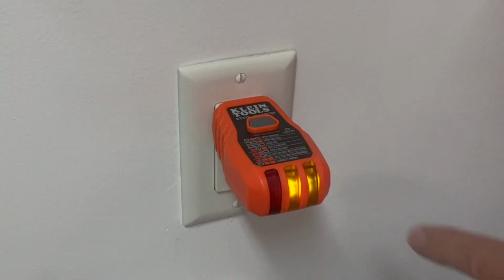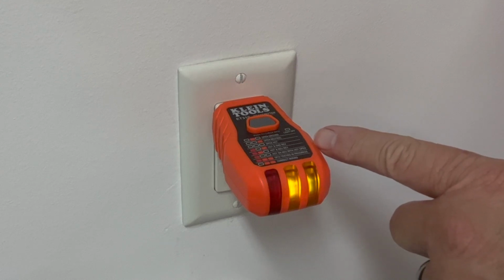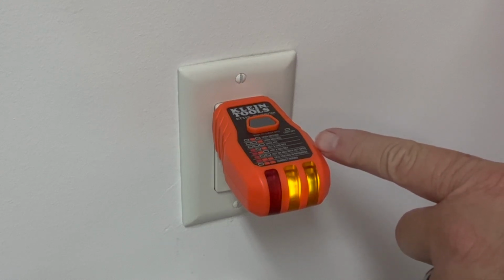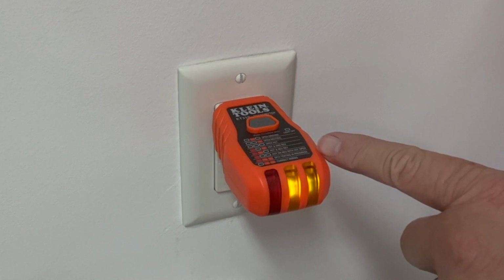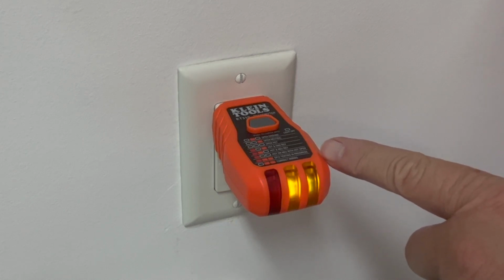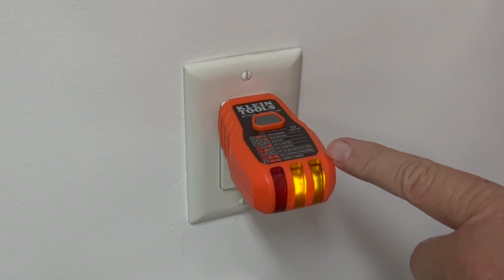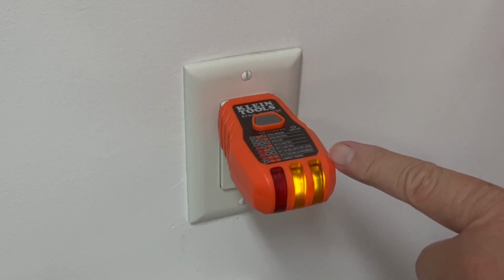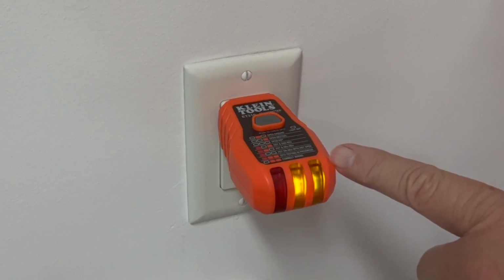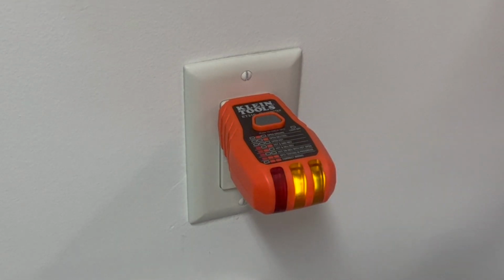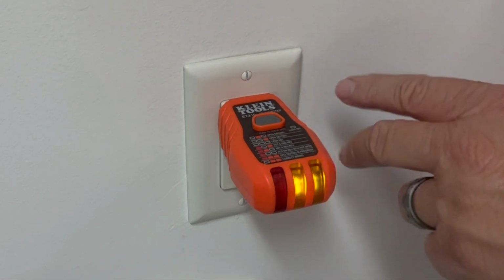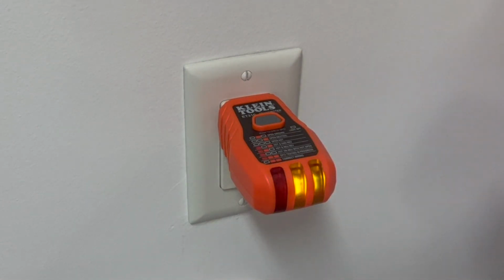So some of the various codes are open ground, open neutral, open hot, hot and ground reversed, hot and neutral reversed, hot on neutral with hot open, and then ground fault testing in progress, and then correct wiring. Okay, and you see this little button here. If you push that little button, it will actually trigger and test the ground fault to make sure that it's working correctly. So we'll leave that there, and we'll go back to the panel and scan for this circuit breaker.